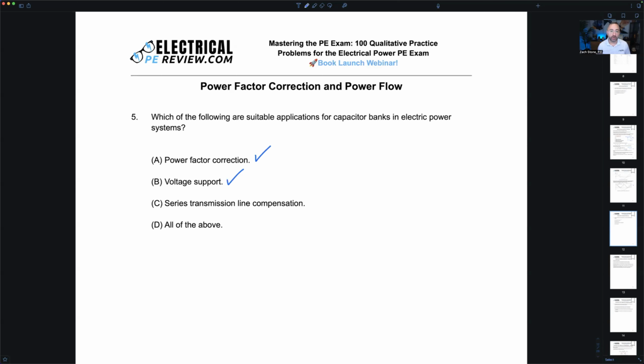And if you're not sure, here's a hint. Think of the National Electrical Code, Chapter 9, Table 9, the table that we use to look up the effective impedance of conductors when we're solving for voltage drop. Are they inductive or are they capacitive? Conductors, when they carry current, they're inductive. Yeah, they're inductive. Good job, Daniel.